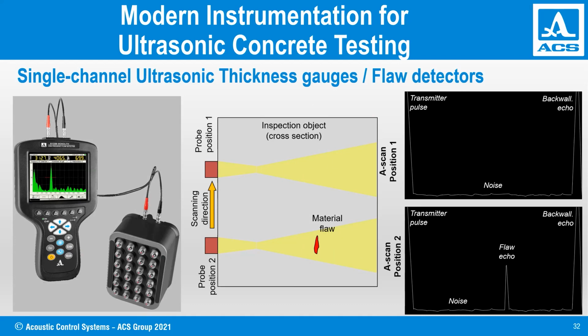We obtain echo signals, and the strongest signal we can ever obtain from the material is the backwall signal. That means the backside of the component. So if we are capable of catching the backwall signal and we know the sound velocity value, we can measure the thickness, and vice versa. If the backwall signal is sometimes disappearing, that means something might be inside.